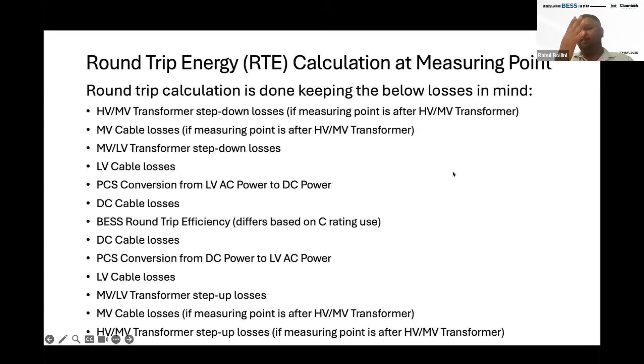And then round trip efficiency - this is a typical thing where people tend to overestimate or underestimate. You need to be very accurate, or else your calculation, financial, everything can go wrong. Typically, it's a two-way calculation where from the transformer there is a cable, then there is a PCS, then there is another cable, then battery, charge discharge, and then again the reverse thing that goes. Yeah, so these are pretty much the things that go.